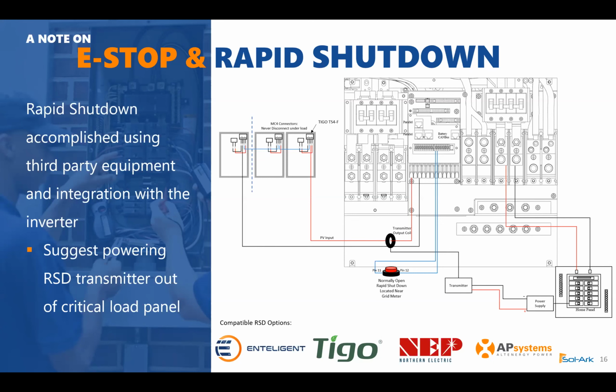I'll talk on that later. So for example, in this wiring diagram, you see two different ways to connect a transmitter. First way, I think it's easiest. You can just connect the transmitter to a power supply on the backup panel, and you can put a normally open button on pins 11 and 12 inside the Sol-Ark inverter. What this will do is short the entirety of the AC connections of the Sol-Ark, power it down, and disconnect power to the rapid shutdown power supply of the transmitter. Once the transmitter goes offline, it's going to stop sending the keep alive signal to the receivers connected to the solar panels on the rooftop. That will activate and lock in rapid shutdown, so you'll be in compliance there.